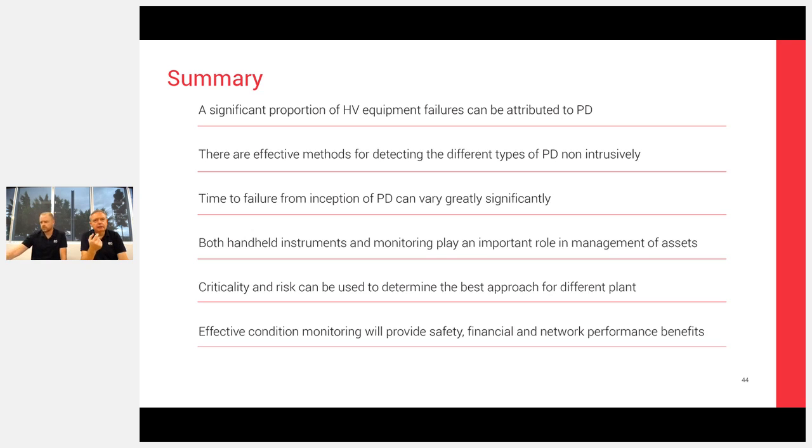And the other aspect is, are you really interested in the exact number? Is it 23 dB or 24 dB? Or are you interested in the alarm capability and the function and what is changing and trending? So if one of the sensors were, for example, to drift, so it's reading 1 dB out, fundamentally, it's not realistically going to make much of a difference in terms of the answer and the diagnostic. But typically you can go in there, say every 2 years, and check each of the individual sensors.